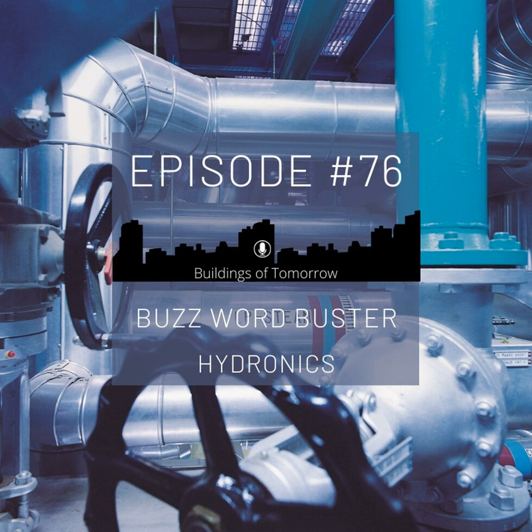And so that's again a situation that we want to see more and more in the future, either throttling circuits as discussed before, or injection circuits with two-port valves. And these two circuits, by using two-port valves, are the preferred approach, because if we use a three-port valve, we're pumping water around in circles for no particular reason. Is that correct? It's correct in certain applications.